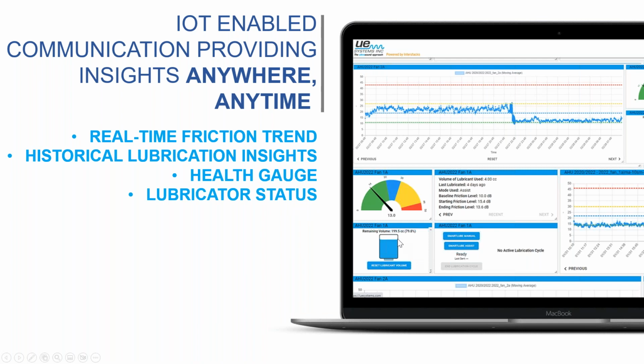And we have the lubricator status. So we know out there, hey, lubricator, are you happy out there? Are you doing good? I know you're sitting out there on an island all by yourself, all lonely, right? Essentially, it's just sitting there sleeping for the majority of its life. We want to know, hey, when I ask you to lubricate, are you going to wake up and do you have enough grease? Is grease hitting the bearing? So in this case, we probably don't need the decimal point, but right here I can say in this system that there's about 80% of grease left. You can set up alerts to whatever you'd like in order to reorder or fill up that grease cartridge.